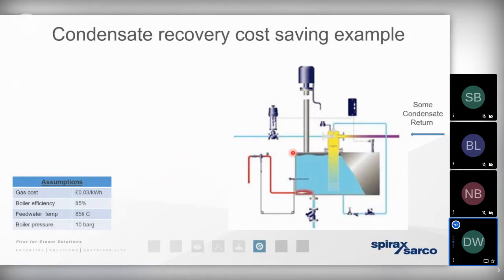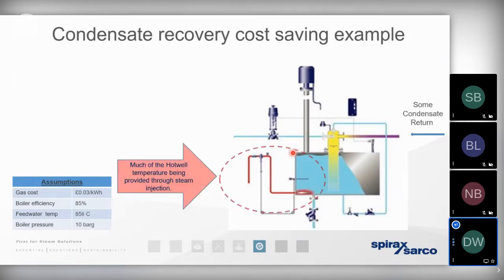And we may never have actually thought about measuring the amount of condensate that's coming back into the boiler house. And it could well be that the temperature of the hot well is held at that high temperature artificially. For example, by using a direct steam injection system to take steam straight from the boiler to add it to the hot well. We've got high temperature hot water, but we don't necessarily have an efficiently operating condensate recovery system. So, of course, it means that we're consuming more and more steam, and also we've got more and more hot water going to waste as a result of that missing condensate.